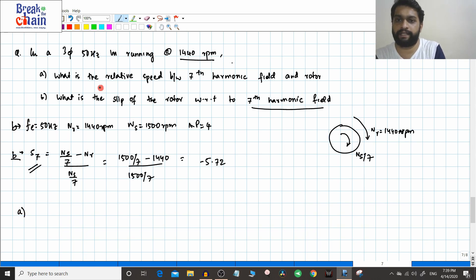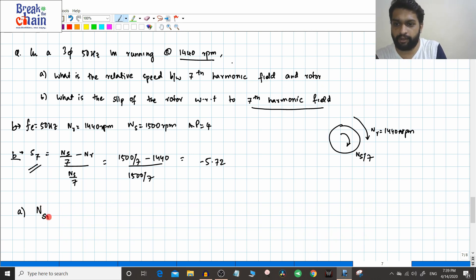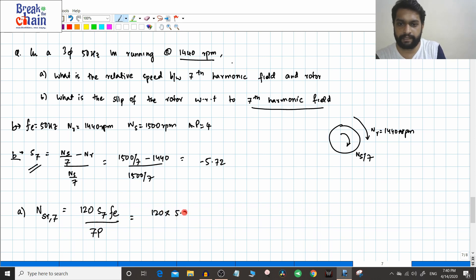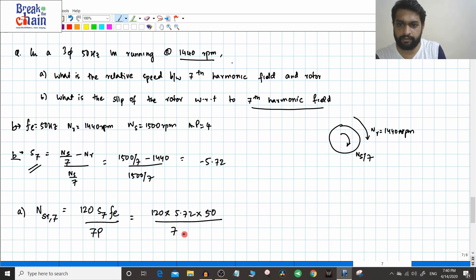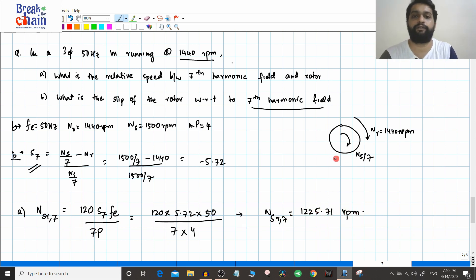For part A, they ask for the relative speed between the seventh harmonic field and the rotor — that is ns_r7 with respect to the rotor. We use: ns_r7 = 120·S7·f_electrical / (7p) = 120 × 5.72 × 50 / (7 × 4). The number of poles p = 4, so 7p = 28. This gives ns_r7 ≈ 1225.71 rpm.